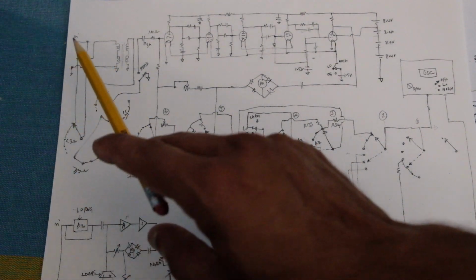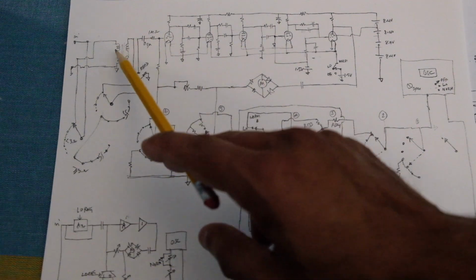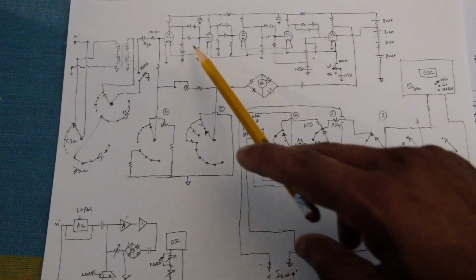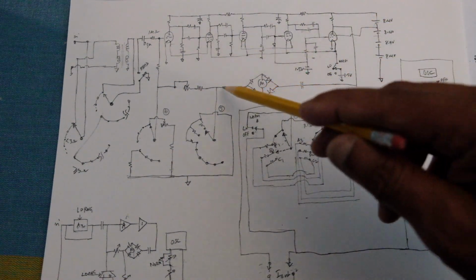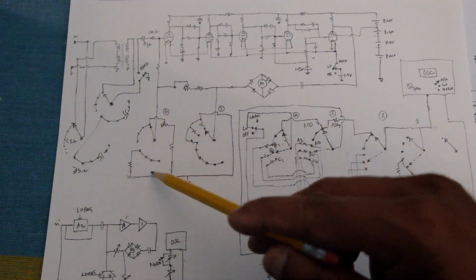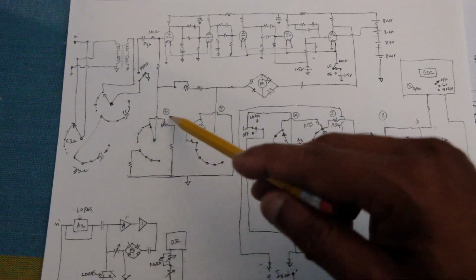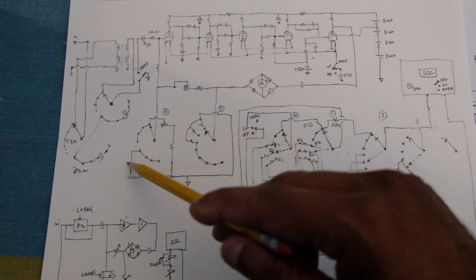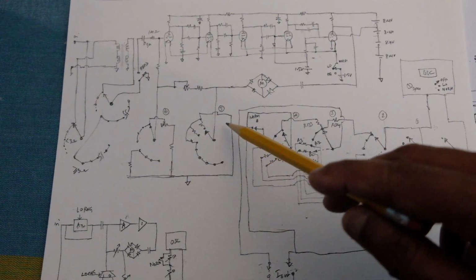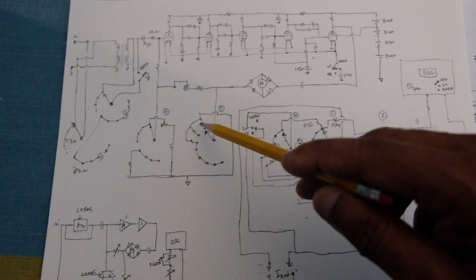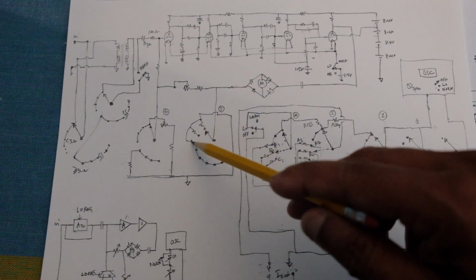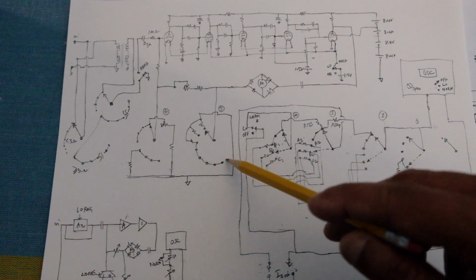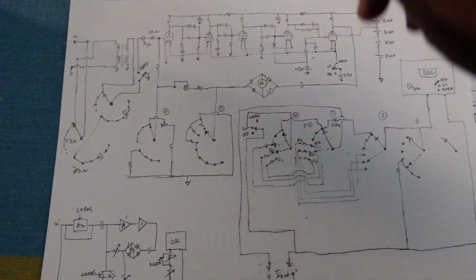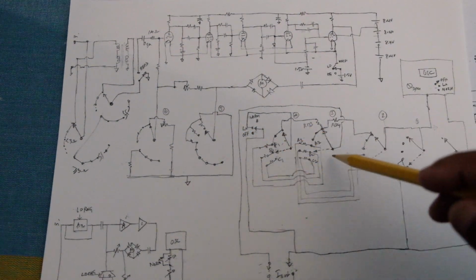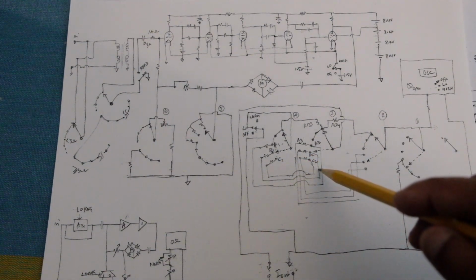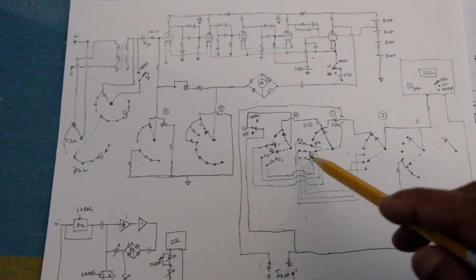And so you can see on the left side is the same transformer-based input that goes for the low range, and then it goes into the same set of amplifiers, and the output goes back here, and then there's this calibration, and then the rotary switch selects for the low range. It's actually using some bypass resistances, as you can see here, which are different for the low and high range, and the bypass resistance is used for this. Again, you can see that for certain ranges there's a resistance, in the other case it's common over here. It's a common one for all these different positions, so it's much easier to follow over here than on that original schematic over there. And this is the normal voltage and the low voltage implementation using two series resistances.